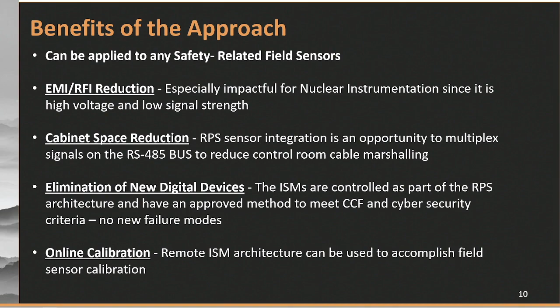The second large benefit, particularly for advanced reactors looking to minimize their footprint, is a significant space reduction by removing the electronics that take in field sensor signals and moving them further into the field. You remove all the field sensor cables that come into the reactor control system, from the 4-20 loops and 0-10 volt loops. All of those components in today's reactor protection systems can be moved into a digital transmission early in the process, and put onto the same digital backplane that the reactor protection system operates under, reducing the number of cables. So what was once a cabinet full of equipment is reduced to just a handful of twisted shielded pair cables.